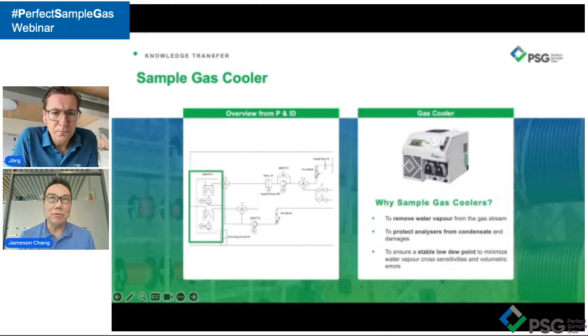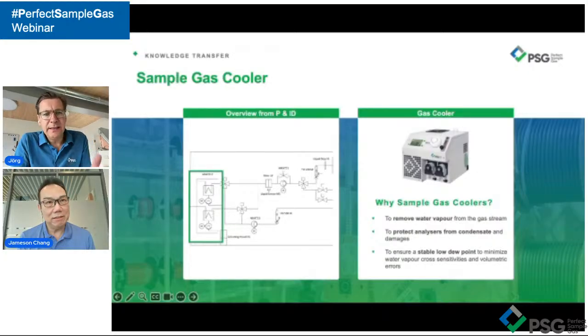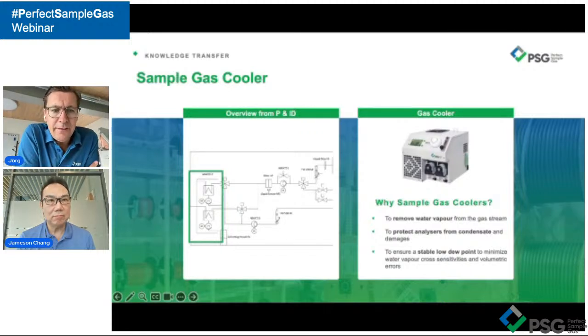In that case, we will choose a hot wet analyzer. So a hot wet analyzer, Jameson, means you still need a heated filter. That means the gas sampling probe, the GSP, has to be heated for sure. Then you have a heated sample line connected to the gas sampling probe, but then the sample itself can arrive hot directly to the analyzer.